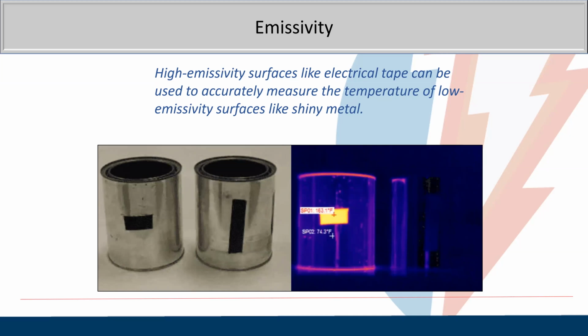One trick, when dealing with a copper transmission line, is to put a piece of tape or some known surface with a known emissivity on it, then calculate the actual temperature if that's what you're interested in. For example, with a transmission line or elbow that's heating up, you may want to put electric tape on it before shooting it with an infrared camera. That will give you a much better idea of the temperature if the meter is calibrated properly.